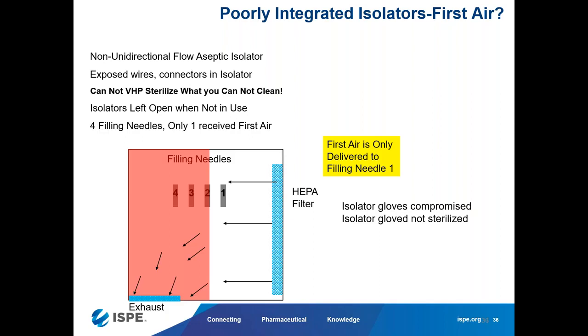The FDA loved the product but did not give them the blessing to manufacture it. Why? We talked about this before: first air to the filling needle, important. HEPA filters on the side. Which needle gets the first air? The first needle. There is no assurance that any other needle will get first air.